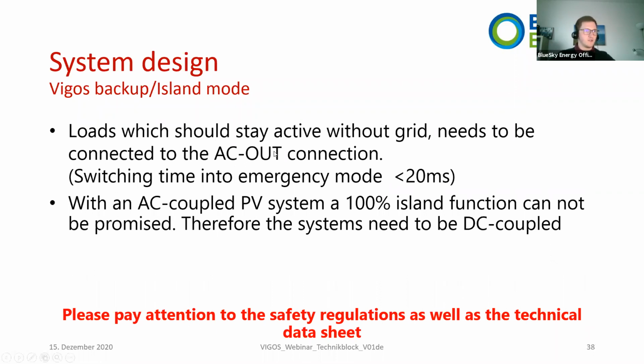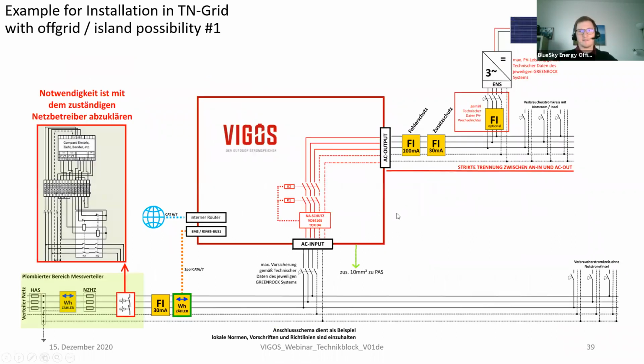So the loads which should stay active need to be connected to the AC out, and also the inverter which should stay active, the PV inverter, should be connected to the AC out. So how will this look? It will look like that. So we don't connect the inverter here. We would now connect an AC PV inverter to the AC out connection.